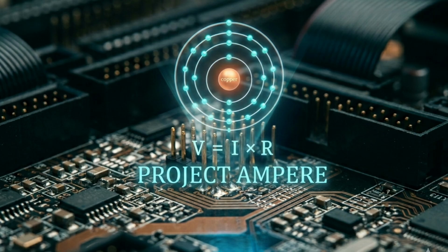A single microscopic strand of frayed copper wire left intact on a massive power cable will make the meter beep happily. A heavily corroded switch contact full of carbon will make it beep. Exactly. But try to actually push 20 amps of working current through that single frayed strand. It will instantly fail or burn up. It will create massive localized resistance. High resistance fundamentally causes a severe voltage drop. So your expensive pump motor only receives 18 volts instead of the required 28. It runs dangerously slow or it overheats.